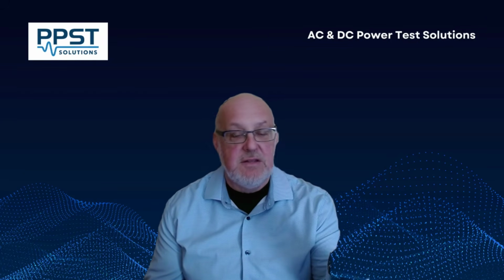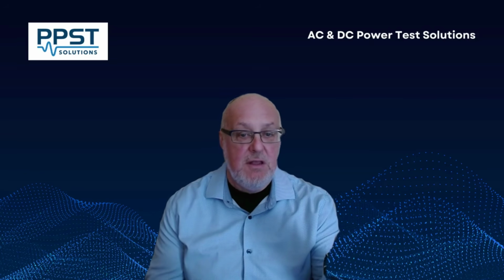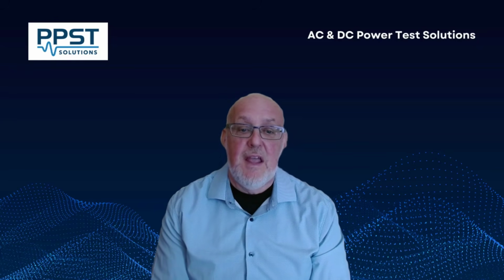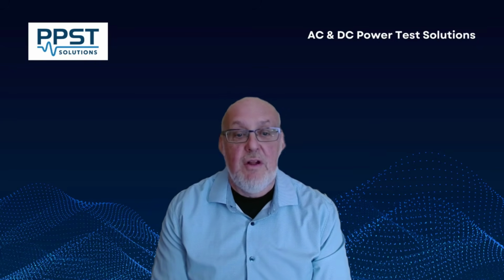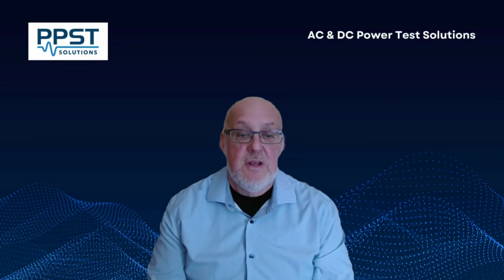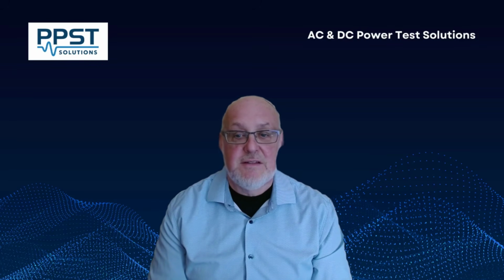There's a lot of reasons to look from a reliability point of view at why relying on the utility is not the most economic sense. You need these other topologies that ideally could be backup as primary. Diesel generators are utilized a lot in the marketplace. In places like California, where there's air quality control, you can only have diesels on for so many hours under emergency conditions before they have to be turned off. And for an AI data center, it's not how they can make money, by turning off and turning back on.